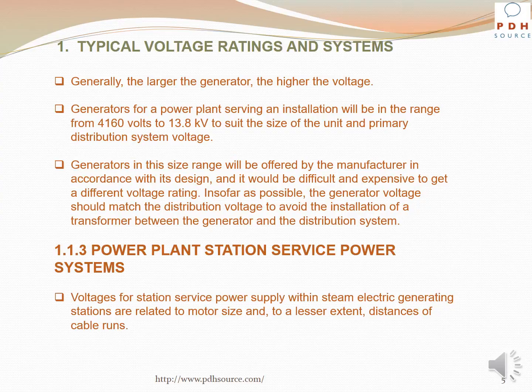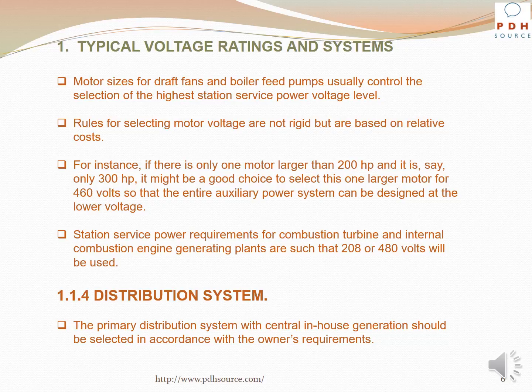With regard to power plant station service power systems, voltage for station service power supply within steam electric generating stations is related to motor size and, to a lesser extent, distances of motors. Motor sizes for draft fans and boiler feed pumps usually control the selection of the highest station service power voltage level. Rules for selecting motor voltage are not rigid, but are based on relative costs. For instance, if there is only one motor larger than 200 horsepower and it is, say, only 300 horsepower, it might be a good choice to select this one larger motor for 460 volts so that the entire auxiliary power system can be designed at the lower voltage.